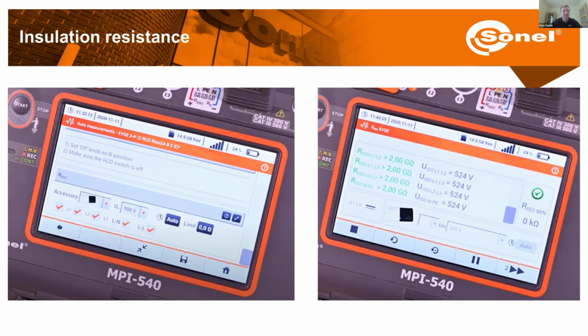So at Sonel, the meters have an automatic test sequence here for insulation resistance. Once you connect the meter to the socket on the charging station or to the cable on the charging station, it will automatically perform insulation resistance measurement between each pair of the wires. And on the meter, like you can see here, we can check the right boxes before the measurements, which wires we have in a charger, what is the configuration here. And after the measurement, we will see the list with the results with all of the combinations.